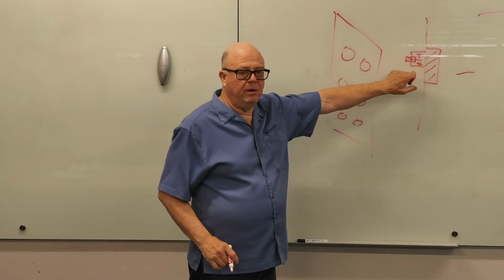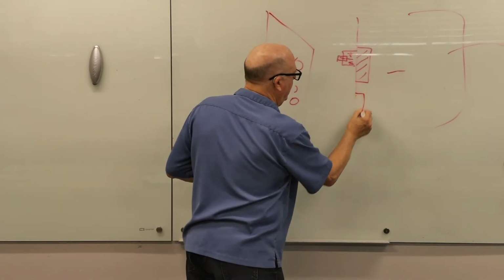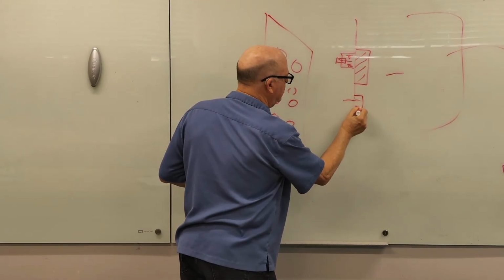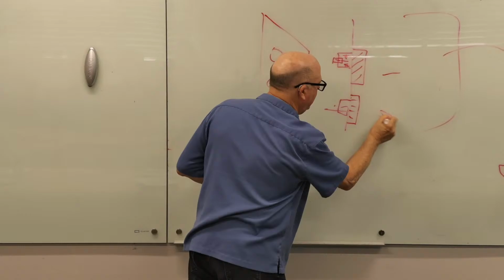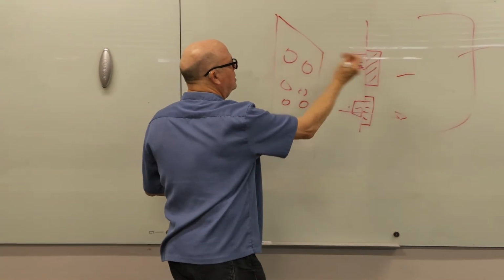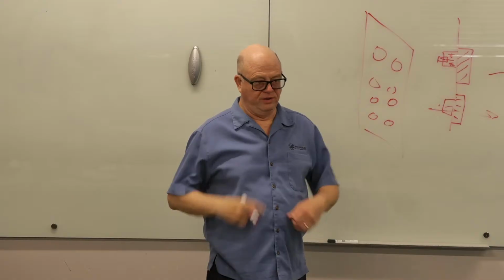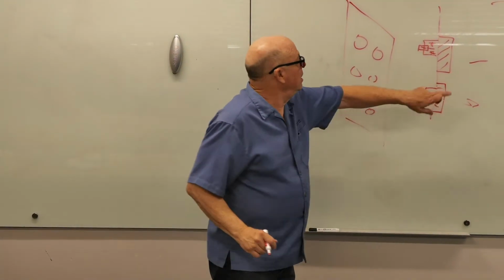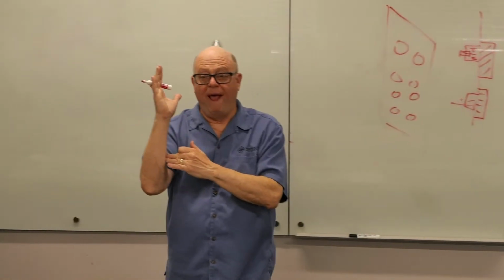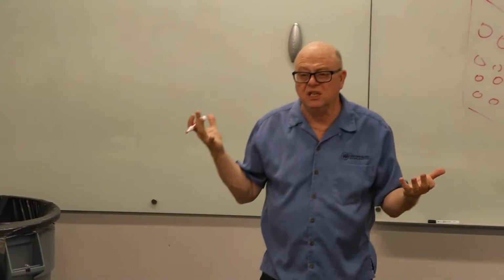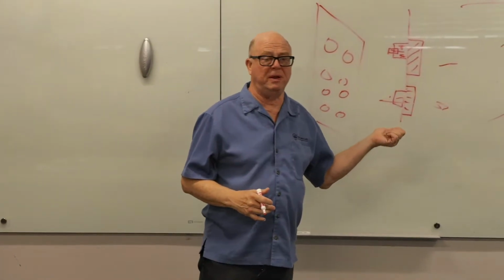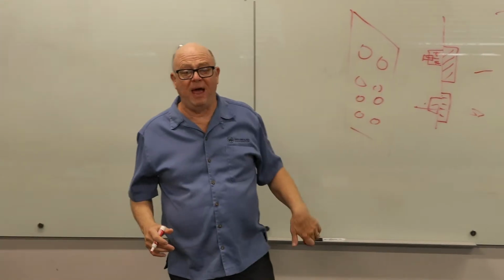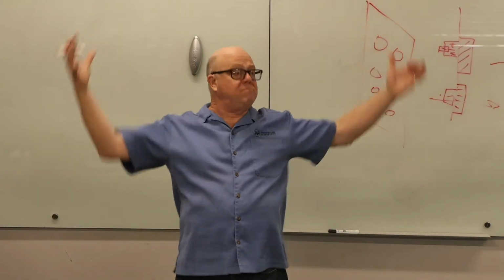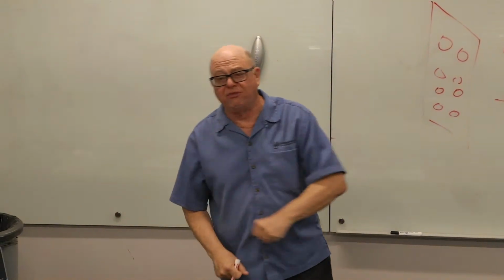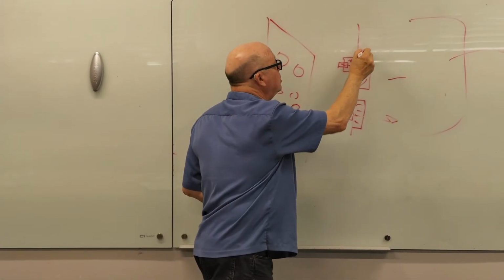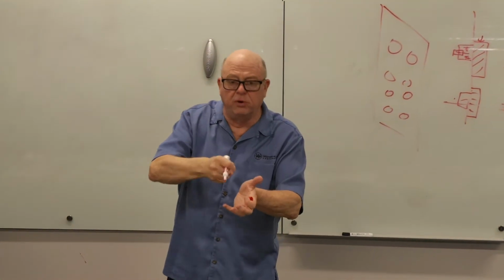Because you've shut the damper, remember we got a whole bunch of these in a row, right? And so here, this one's open and this fan's running and we're pressurizing this plenum. It'll inevitably start going back through here and spinning the fan backwards if we haven't shut it off. And that's got to have a decent seal, because if there's any leakage at all, it will start the fan spinning backwards. And if it starts the fan spinning backwards and it's an ECM motor, it can't stop and go back the other direction.